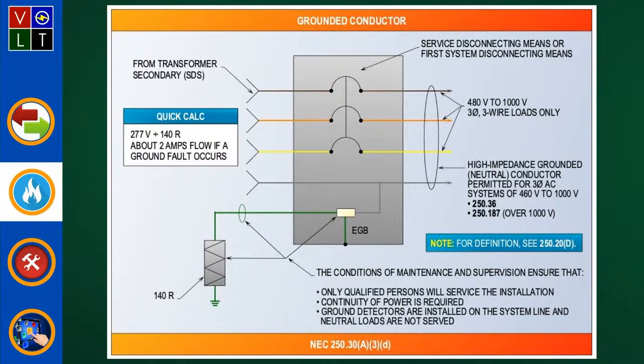Now this next one is impedance grounded systems. Basically you can have a grounded neutral conductor for an impedance grounded neutral system, but if you're going to do that, it has to be installed per 250.36 and 250.187, which say it has to be a 3-phase AC system of 480 volts to 1,000 volts. We show that in the illustration.